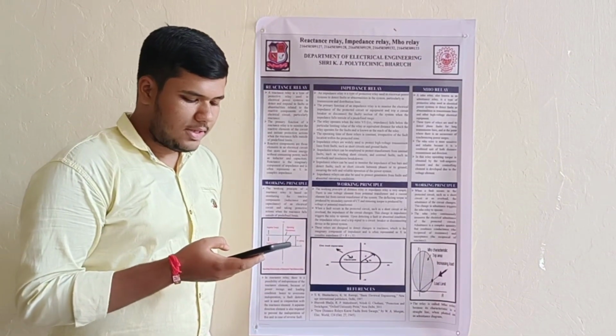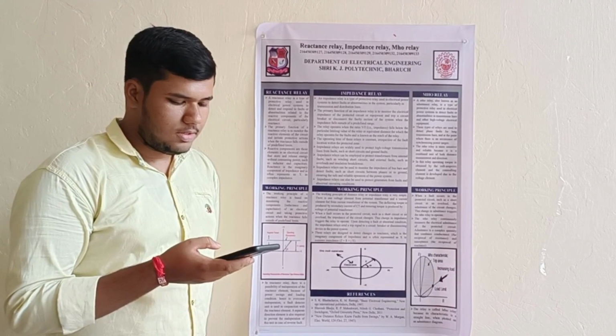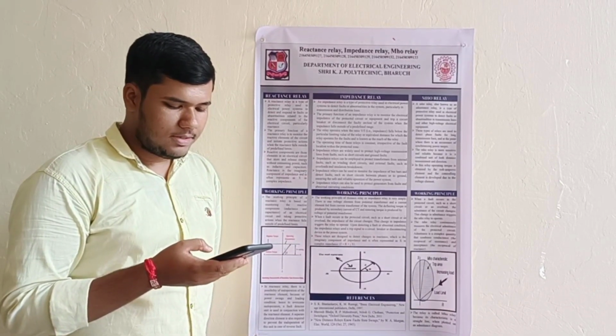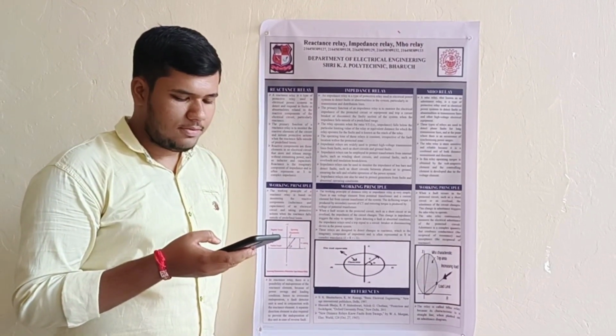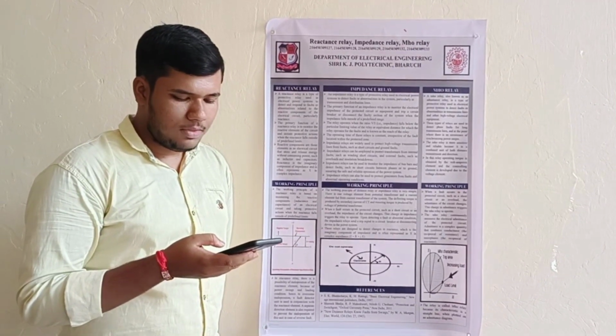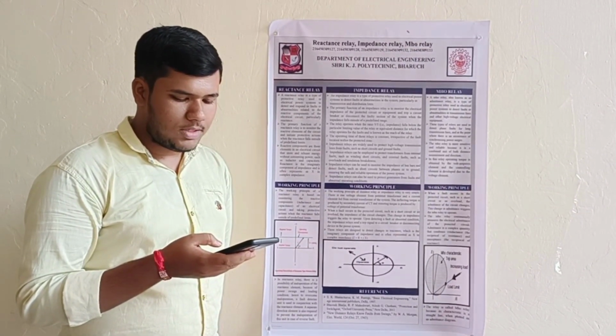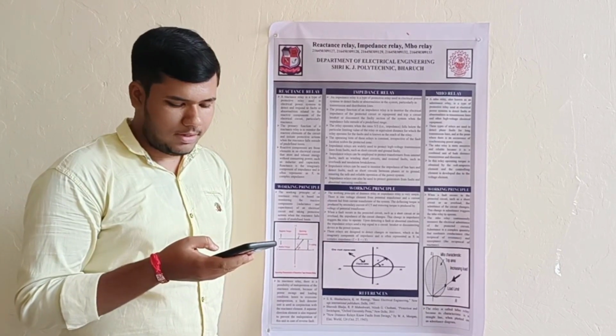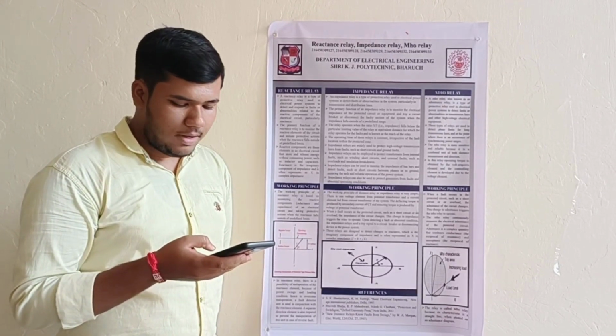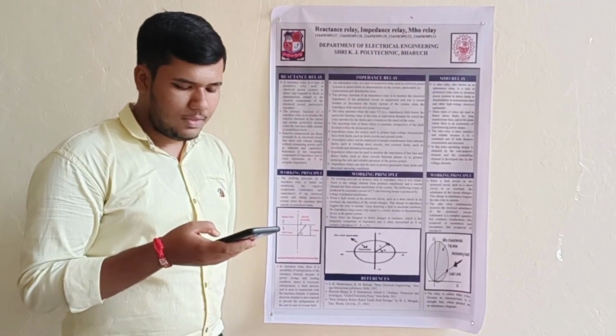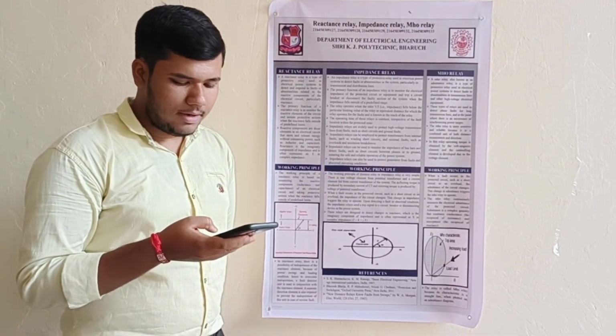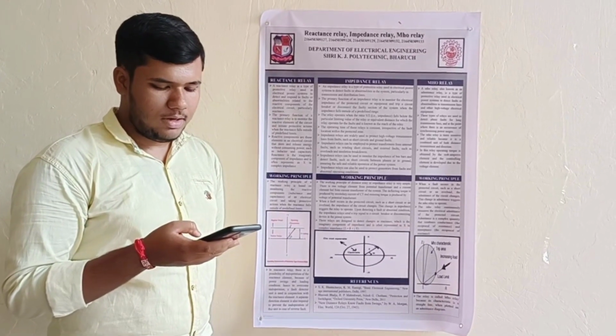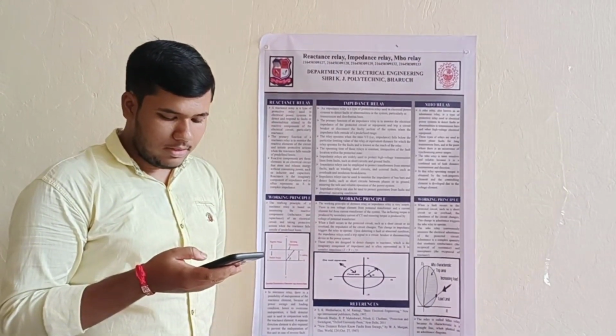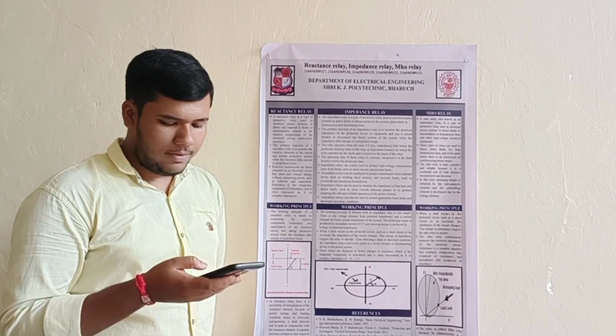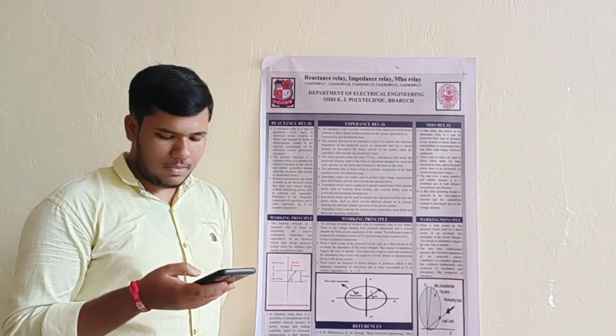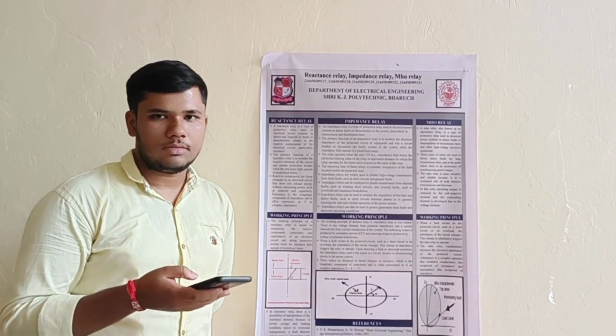Now the third one is sensitivity to system changes. Reactance relays can be sensitive to changes in the system such as variation in load or overvoltage. This can result in false tripping or inaccurate fault detection. Now the fourth disadvantage is limited functionality. Compared to other types of relay, reactance relays may have limited functionality and features. They may not be able to perform advanced functions like communication or coordination with other relays.